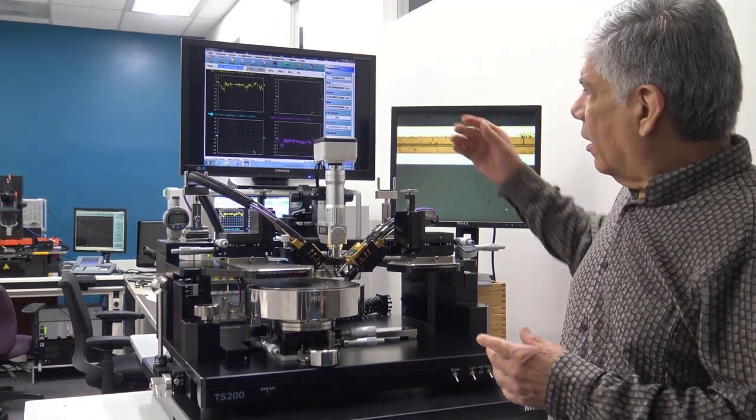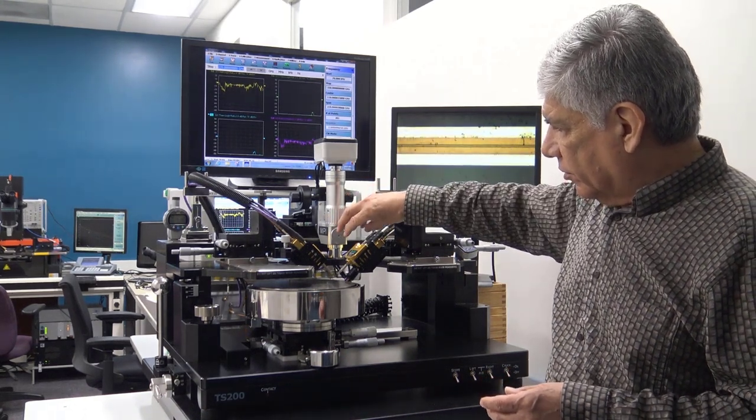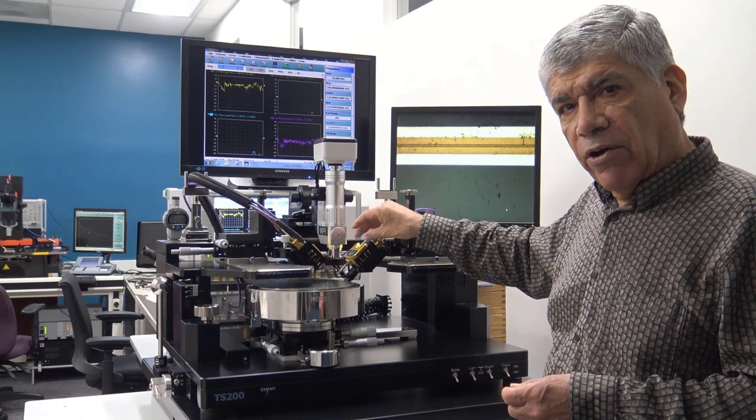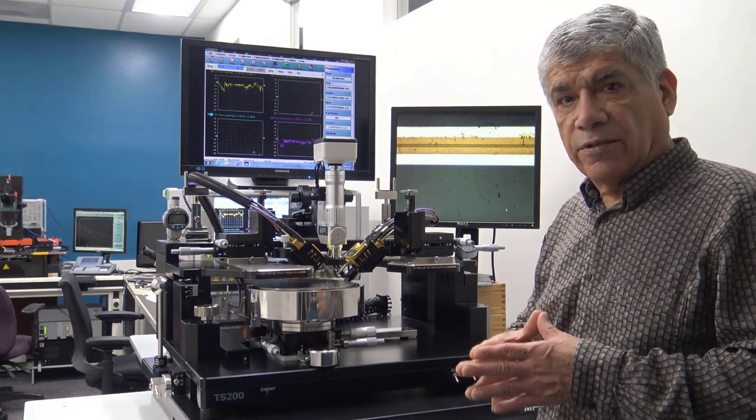A typical application for this system is on-wafer measurements, and therefore what we'll be demonstrating is how to perform an on-wafer calibration for this system, all the way up to 220 GHz. The system is comprised of the VNA and the test set and these modules, and what we have mounted for now is the MPI probes, and we'll be using MPI calibration substrates as well.